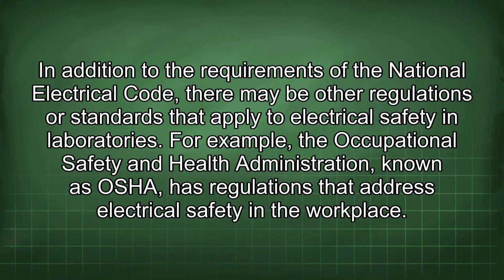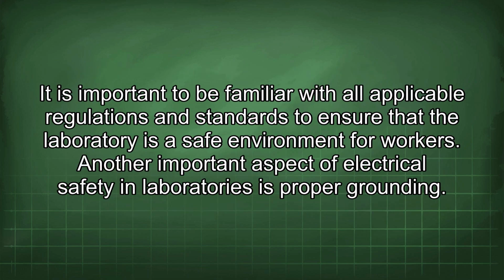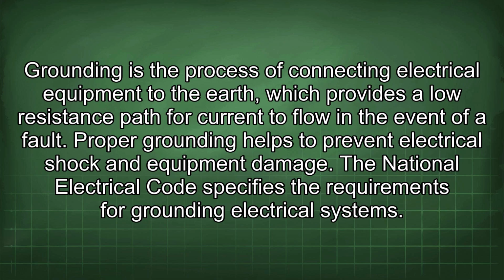In addition to the requirements of the National Electrical Code, there may be other regulations or standards that apply to electrical safety in laboratories. For example, the Occupational Safety and Health Administration, known as OSHA, has regulations that address electrical safety in the workplace. It is important to be familiar with all applicable regulations and standards to ensure that the laboratory is a safe environment for workers. Another important aspect of electrical safety in laboratories is proper grounding. Grounding is the process of connecting electrical equipment to the earth, which provides a low resistance path for current to flow in the event of a fault. Proper grounding helps to prevent electrical shock and equipment damage.